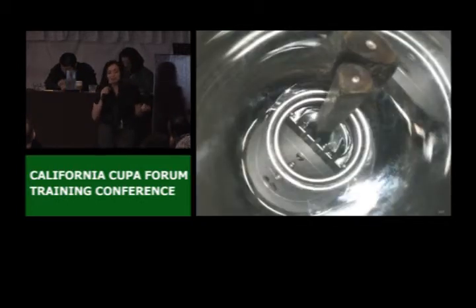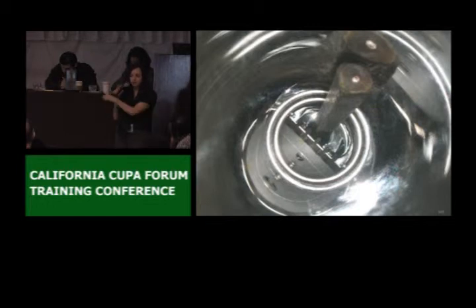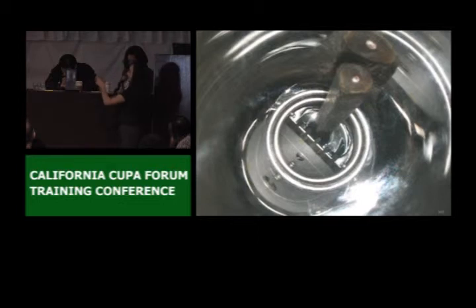Now, if there's a flapper, it has to be working. If there's a wooden stick inside the probe, it's not gonna work because it's gonna block the flapper from actually doing its function, which is blocking the fuel going into the tank, right? So even when we do not test the flapper valves, just make sure that you take a look at it, and you can see that it's gonna work. If you see anything like this, the overfill prevention system that they have is not working. That's a violation that they need to correct. And that's a violation that can be corrected right away.